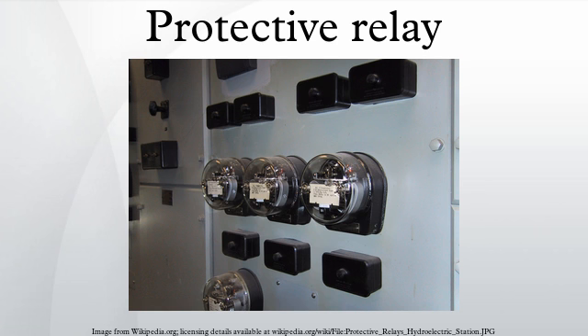Digital relays can, for example, store two sets of protection parameters, which allows the behavior of the relay to be changed during maintenance of attached equipment. Digital relays also can provide protection strategies impossible to synthesize with electromechanical relays, and offer benefits in self-testing and communication to supervisory control systems.